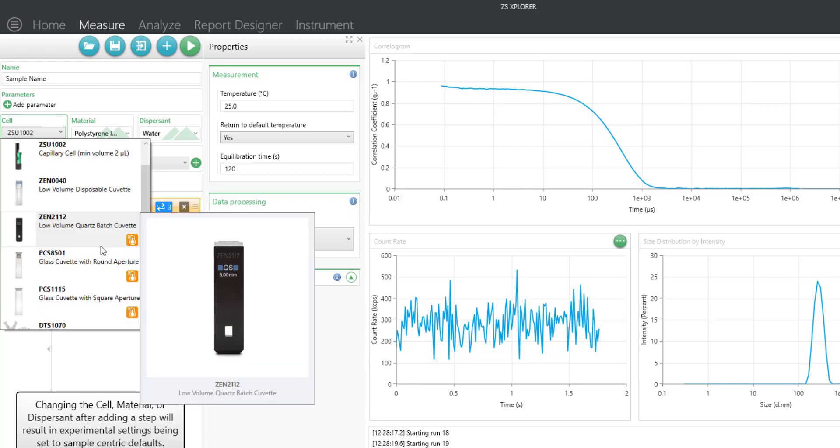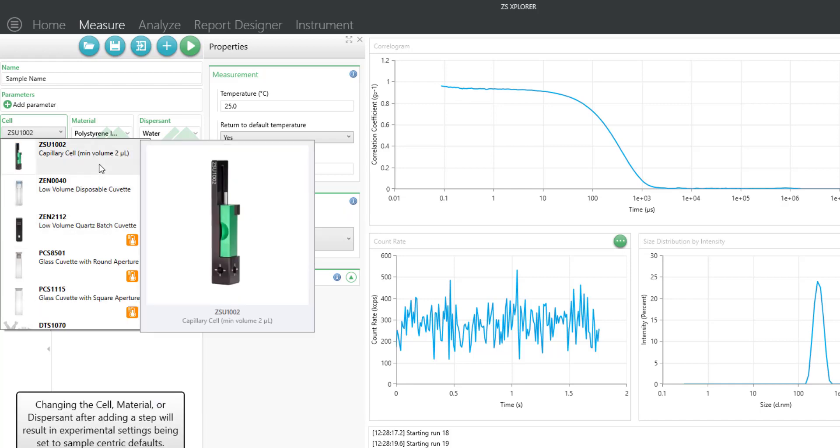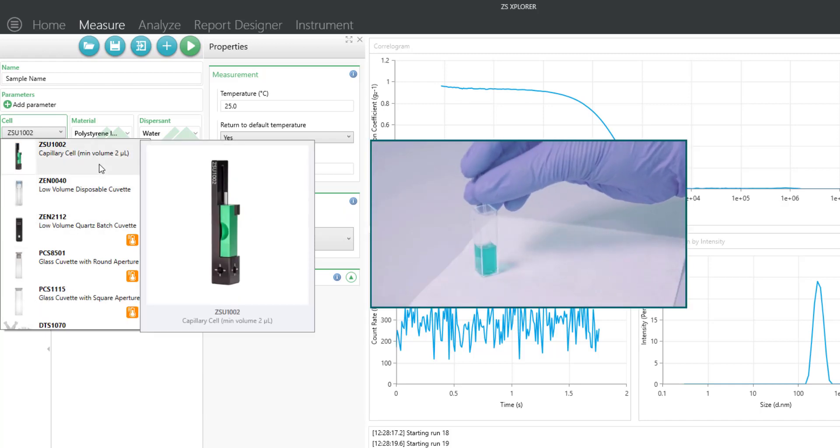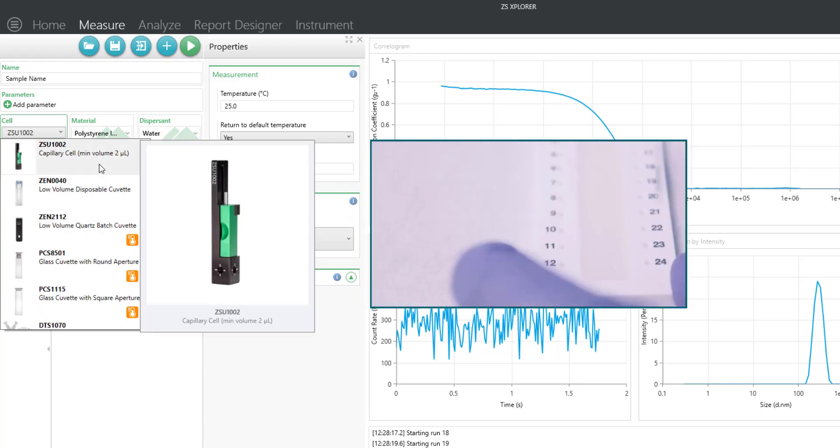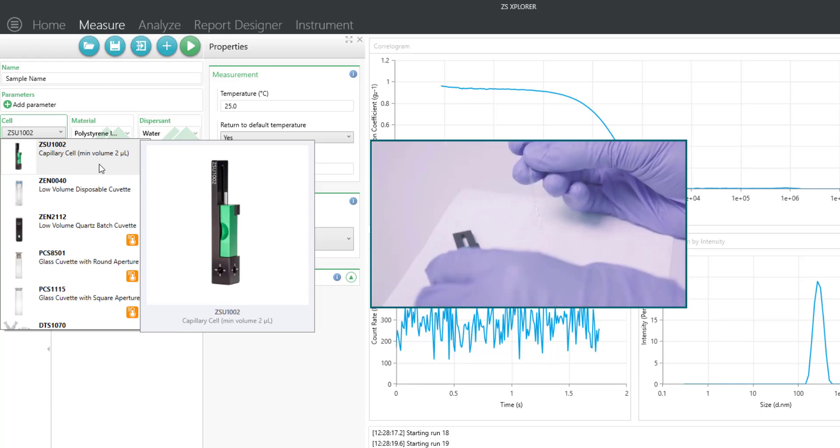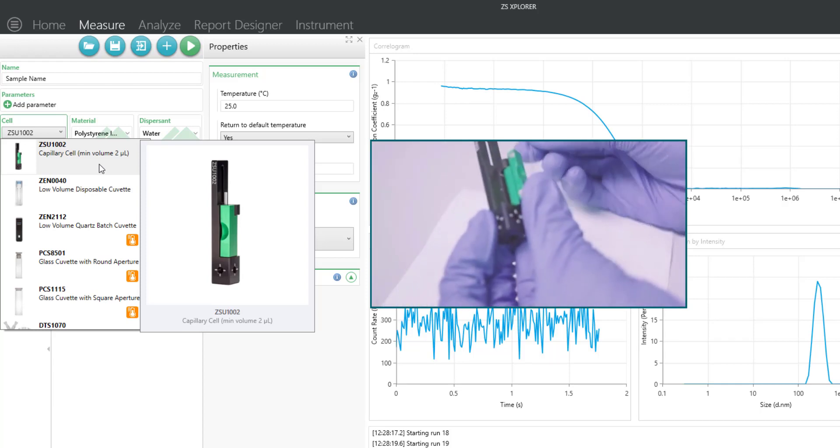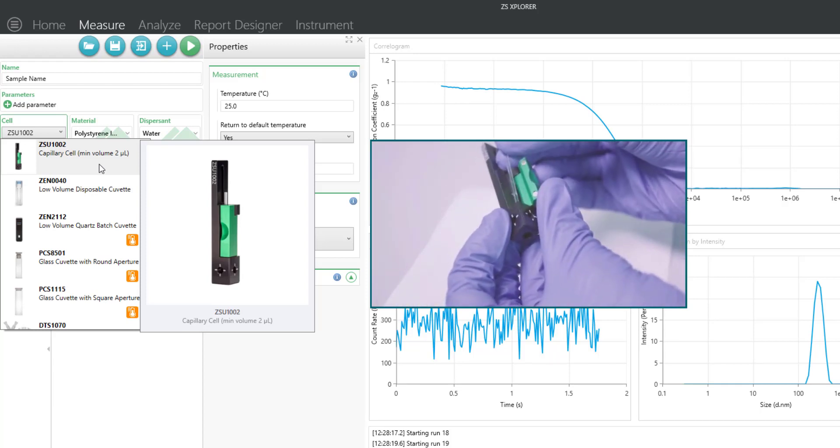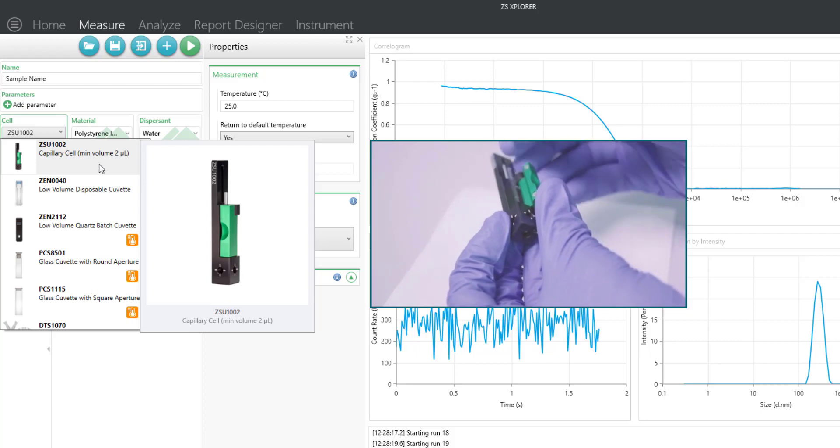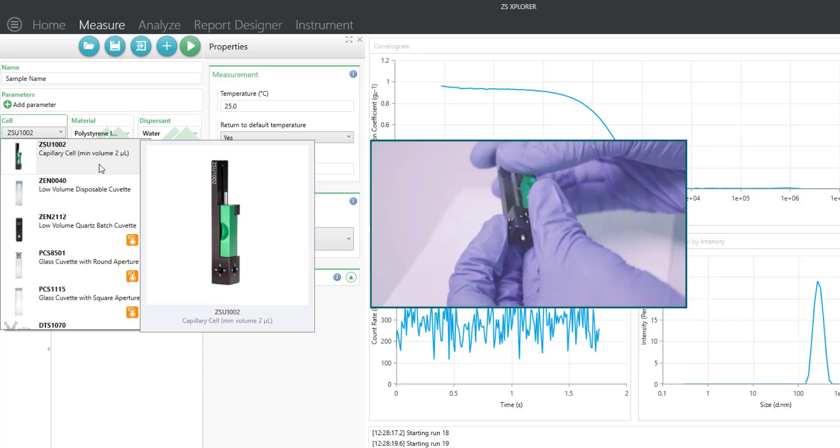The last cell I'll mention is the capillary cell. This cell can use as little as 2 microliters, and it's really good at measuring particles that are very large in size, maybe in the micron range.